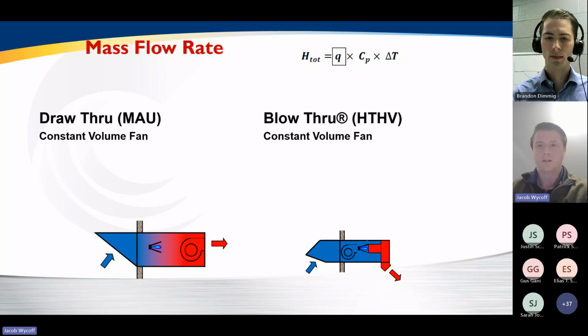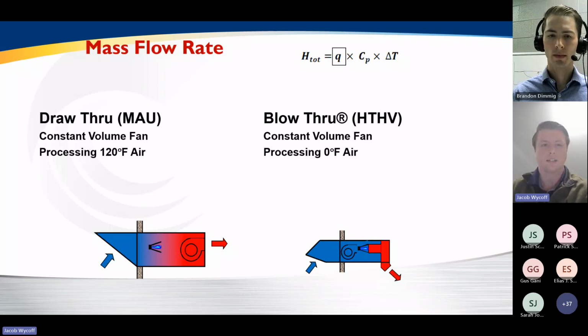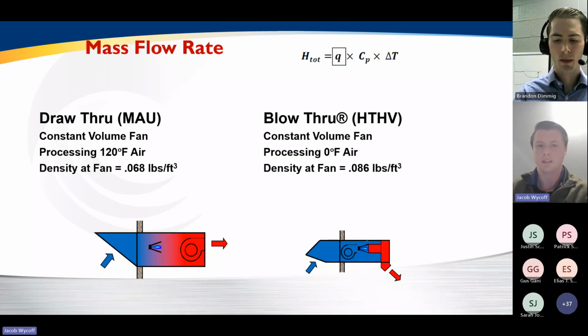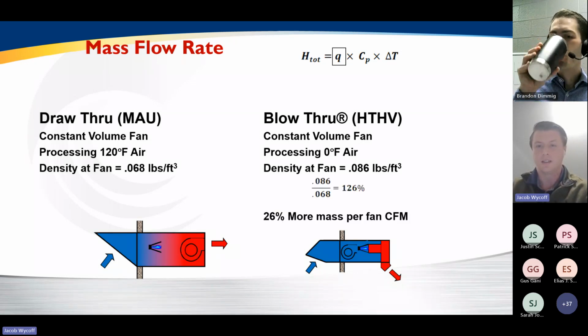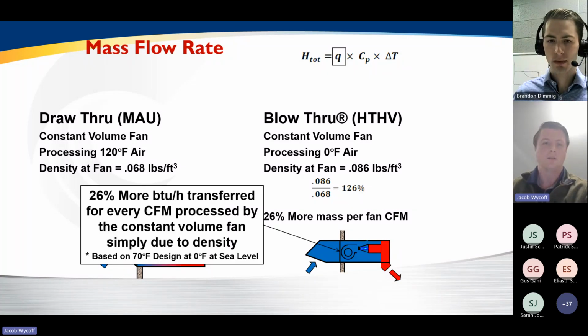So our mass flow rate formula we see up there still at the top right. We know that our mass flow is directly proportional to the amount of BTUs we're providing per CFM. Our draw-through unit is processing 120 degree air at the fan, while our blow-through unit is processing that 0 degree air. That 0 degree air is going to be much more dense. 26% more density, 26% more mass per fan CFM, which directly correlates to 26% more BTUs transferred for every CFM processed by that constant volume fan, just simply due to the density that we're seeing at that fan.